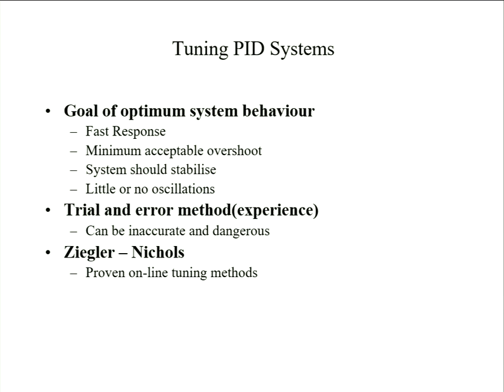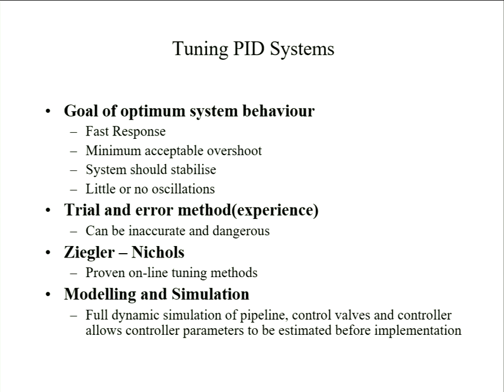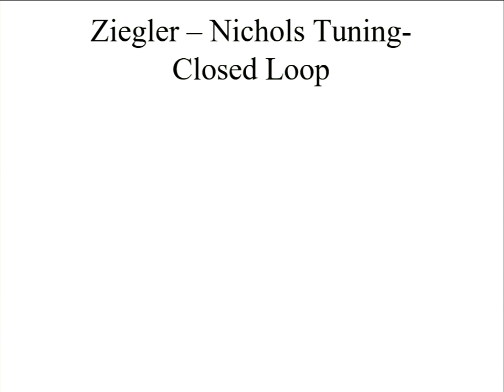So, two types. Closed loop: you set your integral and derivative to 0, so you're in proportional control, and you crank up the gain till it just starts to oscillate. That might not sound like a very comfortable thing to be doing, because you're increasing the gain until you get a certain level of oscillation. You can measure the oscillation period and then feed into equations. So it's a bit like a recipe. The gain that you've increased it to is this critical gain here. What Ziegler-Nichols would suggest, if you were going for proportional only, is 50%.